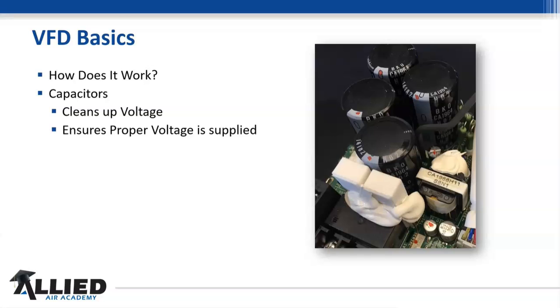What you've got going in is what you're going to have going out. And voltage imbalance on the power system, the motor load, and the impedance of the power system, all that's going to play into the factor of how these VFDs work. So you've got diodes that are controlling the power and the flow of the power. Then you've got capacitors in there that are acting as a reservoir and as a filter for the voltage itself. That's why it's important that we keep really within those percentages that we talked about last week.